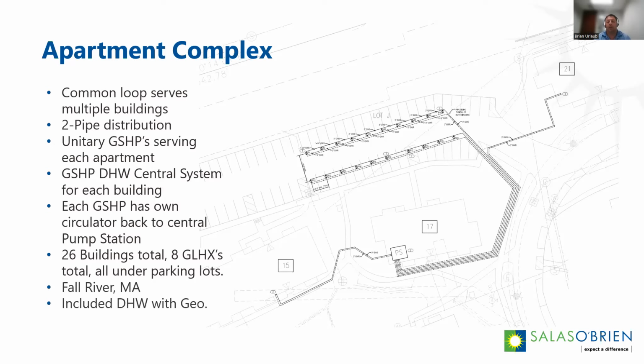So what we ended up with was 3 to 4 apartments combined on one central or common loop, distributing from that one building's pump station out to the other 2 or 3 buildings. The reason we didn't just do one at a time was, number one, diversity, and number two, routing all the piping and having enough space given how the parking lot's laid out—again, constructability. So this is kind of a pseudo district system—mini districts, if you will, interconnected.